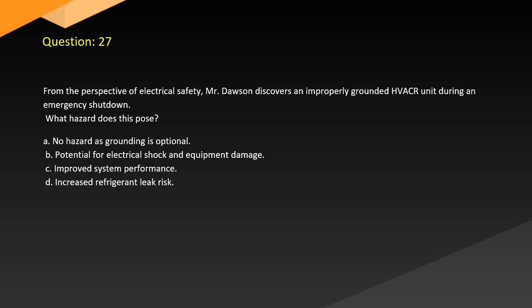Question 27. From the perspective of electrical safety, Mr. Dawson discovers an improperly grounded HVACR unit during an emergency shutdown. What hazard does this pose? A. No hazard as grounding is optional. B. Potential for electrical shock and equipment damage. C. Improved system performance. D. Increased refrigerant leak risk.